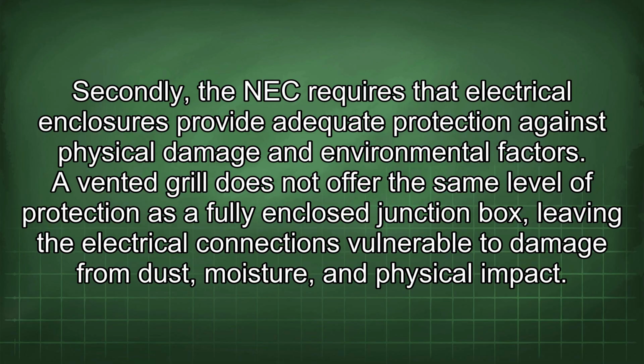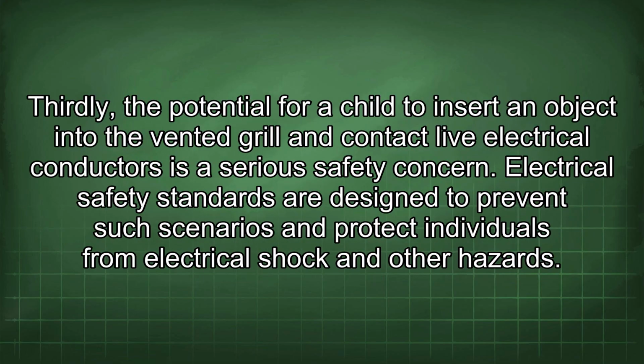Secondly, the NEC requires that electrical enclosures provide adequate protection against physical damage and environmental factors. A vented grille does not offer the same level of protection as a fully enclosed junction box, leaving the electrical connections vulnerable to damage from dust, moisture, and physical impact. Thirdly, the potential for a child to insert an object into the vented grille and contact live electrical conductors is a serious safety concern.